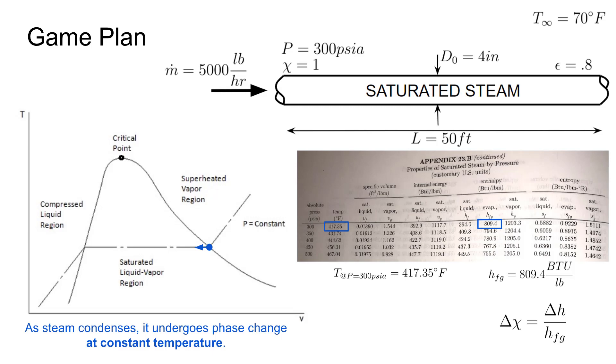So how are we actually going to quantify the decrease in quality? Well, if we can find out how much the enthalpy changes from where it enters the pipe to when it leaves, we can set up a ratio of that delta H compared to the 809.4 BTU per pound, which is the latent heat of vaporization for steam at 300 psi. Note in the steam table, the difference between HF, enthalpy for a saturated liquid, and HG, enthalpy for a saturated vapor, is HFG, the latent heat of vaporization. So delta H is how much heat is actually lost, and HFG is how much could be lost if the quality were driven all the way to zero. So we have HFG, but then to find delta H, we can use Q dot equals M dot delta H.